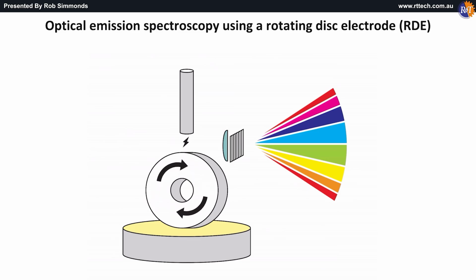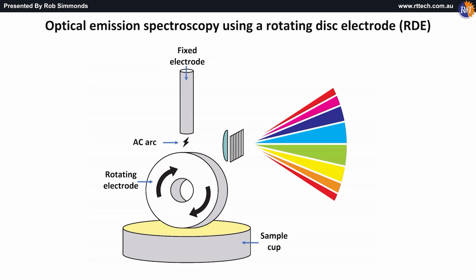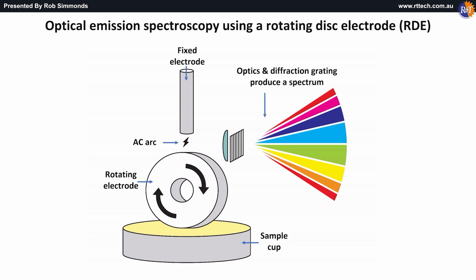Optical emission spectroscopy using a rotating disc electrode, RDE. This is a more manual system with the electrodes loaded in the system individually. The electrode, which has been soaking in the sample for a predetermined period, rotates in a sample cup of the oil. A fixed electrode supplies the arc to produce the plasma dot. The optics and diffraction grating produce a spectrum, which is displayed as the analysis results.